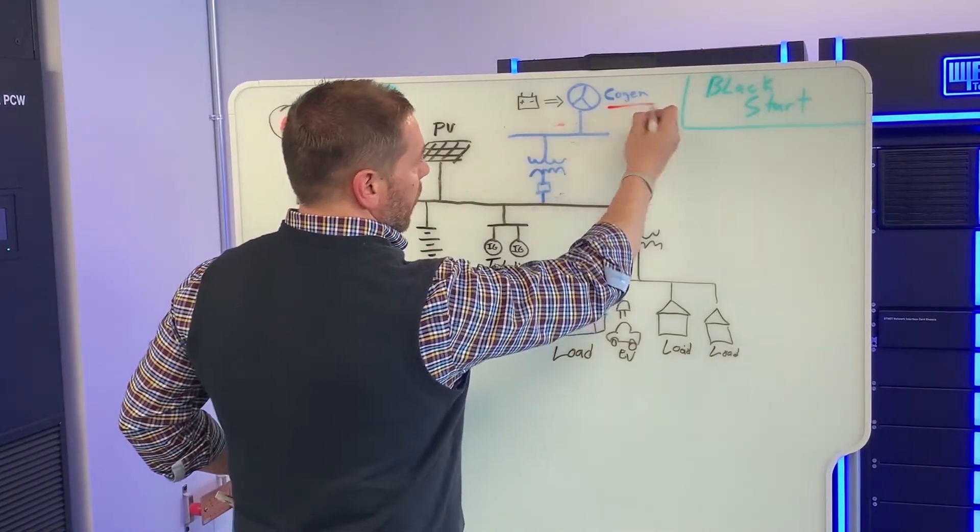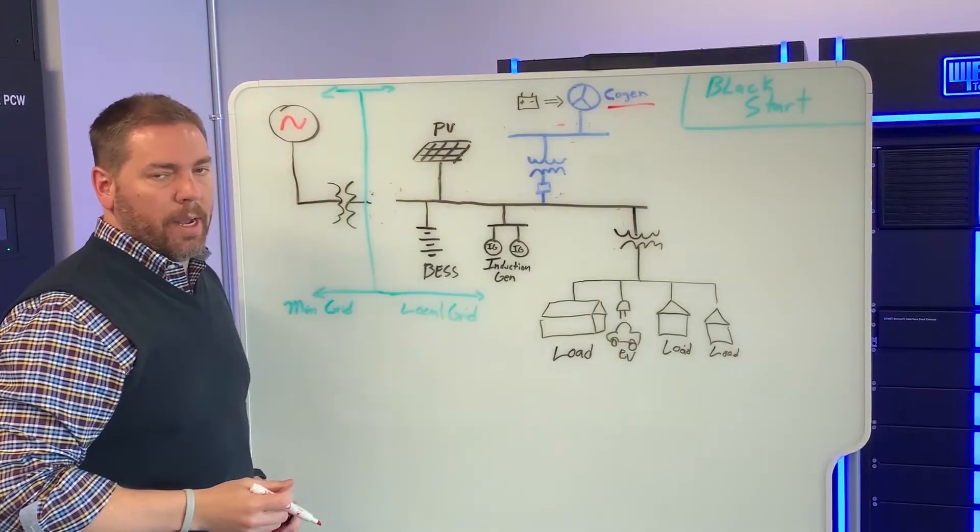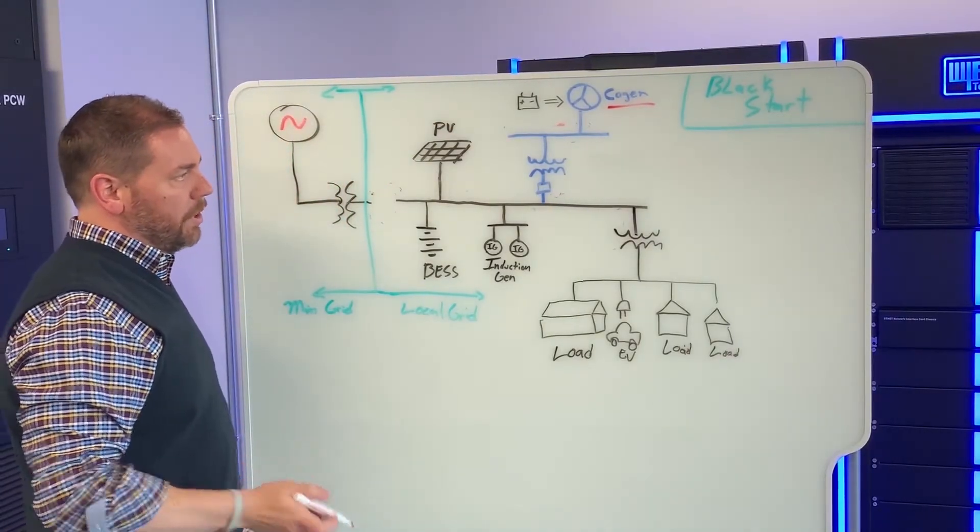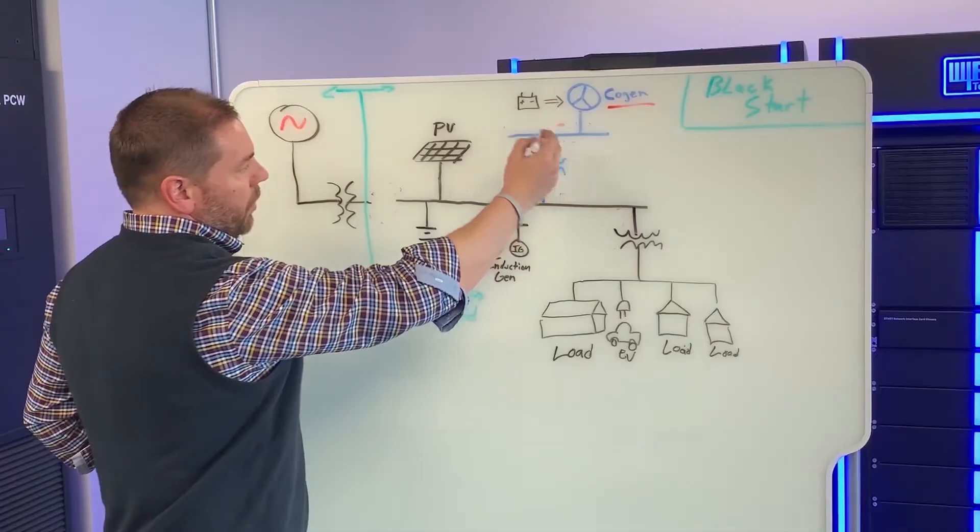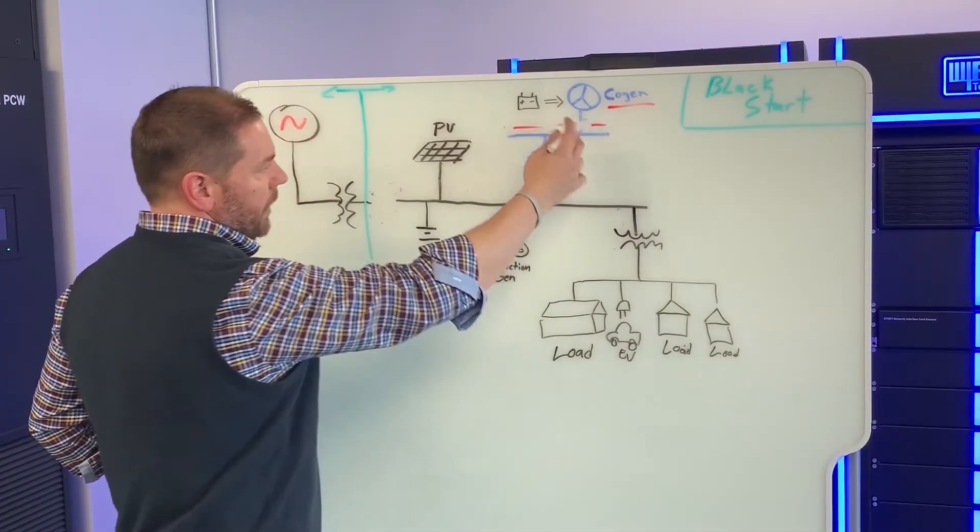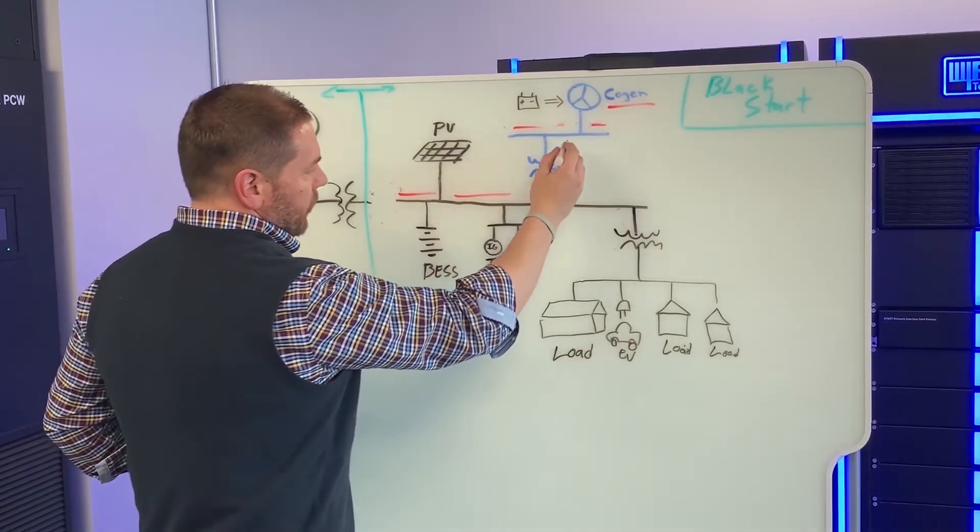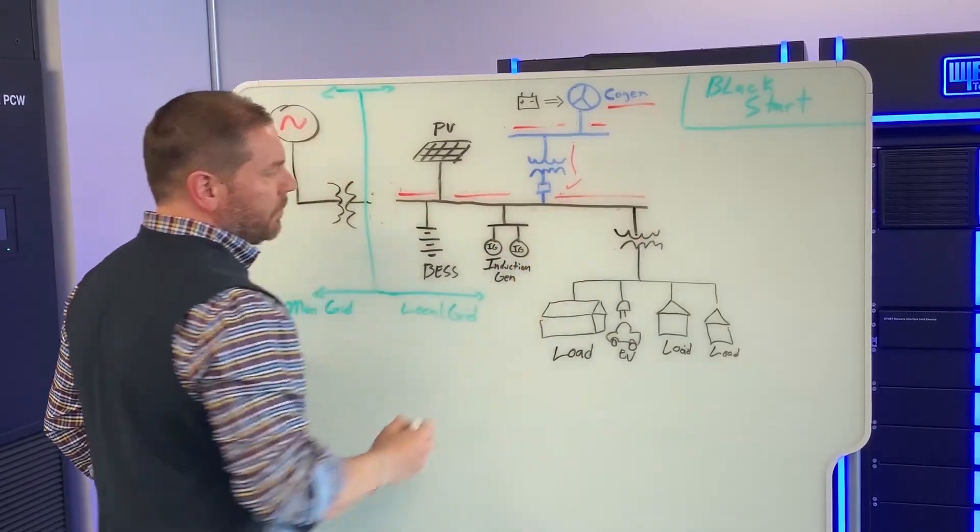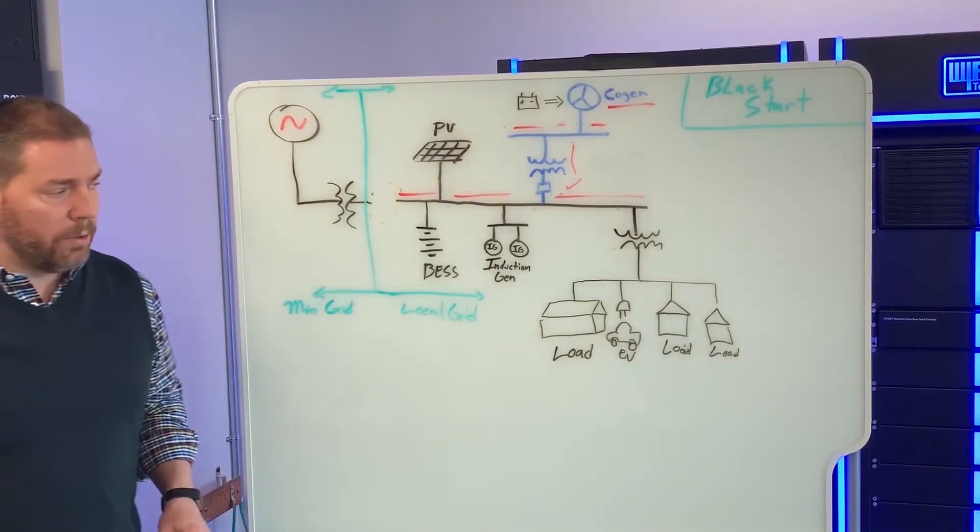We now are, in this example, our Black Start unit is the Cogen unit. The system has started up. We've energized the Cogen bus. We've now energized the transformer and this bus. And now it's ready to take on loads.